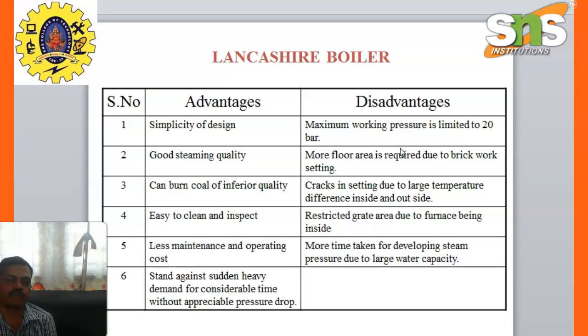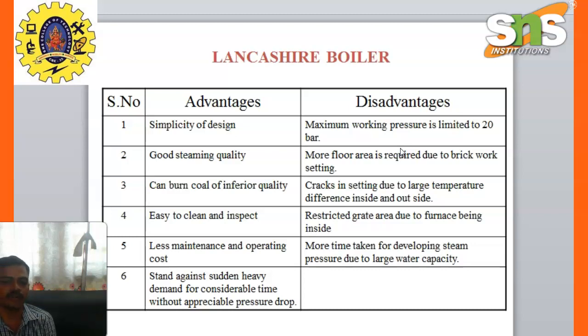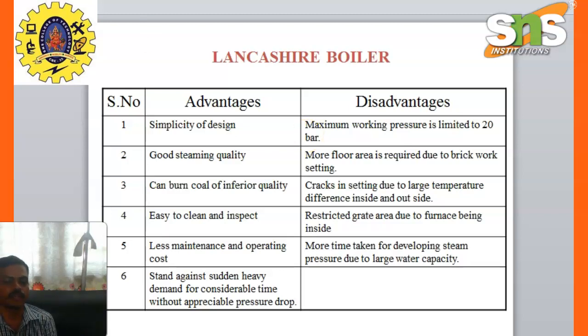The disadvantages of Lancashire boiler: maximum working pressure is limited to 20 bar, more floor area is required due to brick setting, cracks in the setting due to large temperature difference inside and outside, restricted grate area due to furnace being inside, and more time taken for developing steam pressure due to large water capacity.